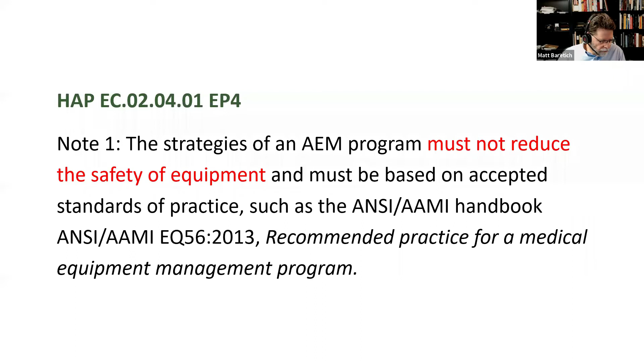It seems like we would want to have been doing that all along, but particularly if we start tinkering with the manufacturer's recommendations. Tinker is not the right word. We're using engineering experience and professional judgment to adjust or modify manufacturer recommendations for PM. We sure as heck ought to know whether we're causing a deterioration in the safety or performance or effectiveness of the equipment. So how do we do that? Next slide, please. So how do we measure equipment safety for the PM program? Next slide. Thanks, Kamisha.